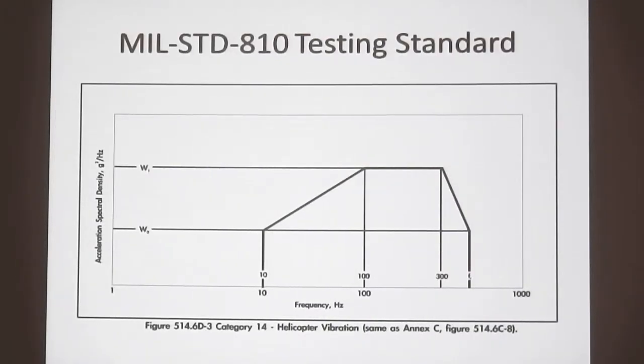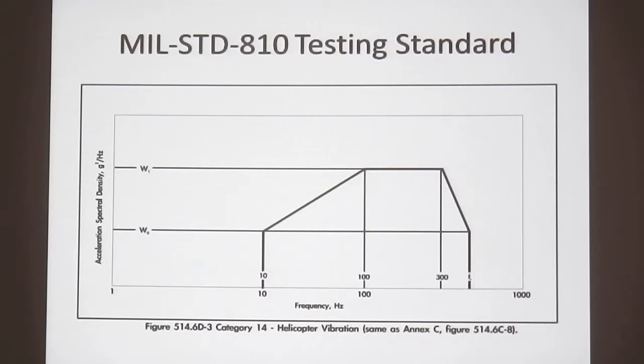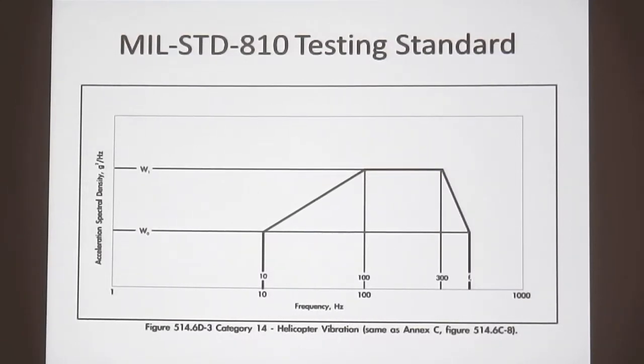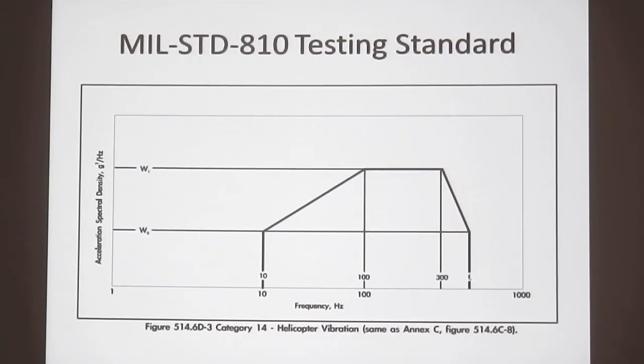This is a curve taken from MIL-Standard 810 for random vibration. If one looks at the curve shown here, what this represents is an envelope. Many tests have been run under actual service conditions, and the results all fit within that envelope. So if your equipment can pass the stresses imposed by that envelope, it will certainly pass in the field.